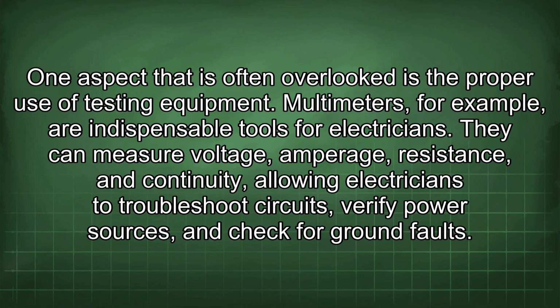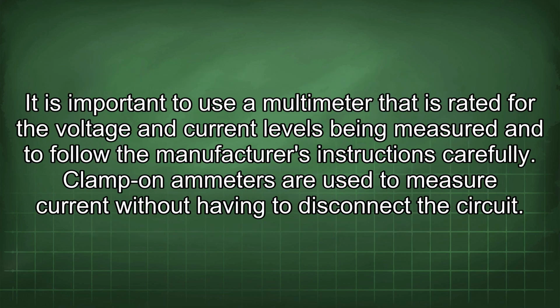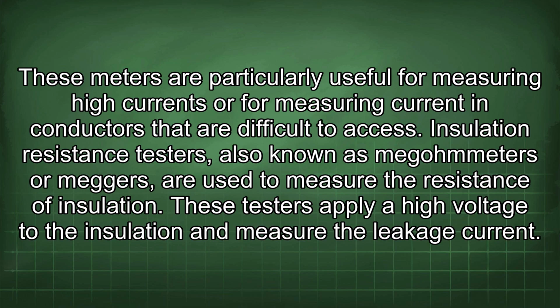Multimeters, for example, are indispensable tools for electricians. They can measure voltage, amperage, resistance, and continuity, allowing electricians to troubleshoot circuits, verify power sources, and check for ground faults. It is important to use a multimeter that is rated for the voltage and current levels being measured and to follow the manufacturer's instructions carefully. Clamp-on ammeters are used to measure current without having to disconnect the circuit. These meters are particularly useful for measuring high currents or for measuring current in conductors that are difficult to access.